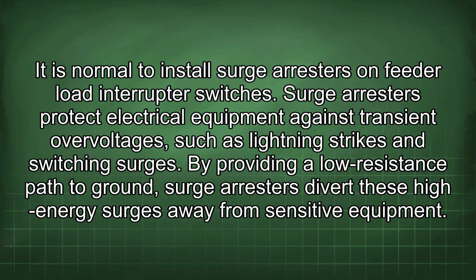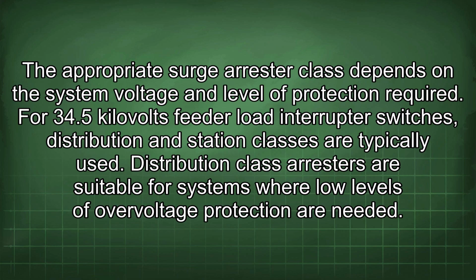It is normal to install surge arresters on feeder load interrupter switches. Surge arresters protect electrical equipment against transient overvoltages, such as lightning strikes and switching surges. By providing a low resistance path to ground, surge arresters divert these high-energy surges away from sensitive equipment. The appropriate surge arrestor class depends on the system voltage and level of protection required.